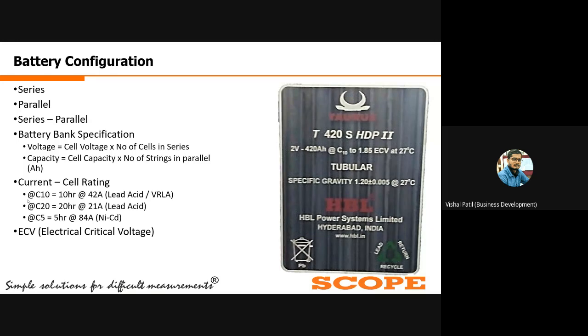So that's why it is very important to maintain the cell voltage above ECV. Generally this ECV is 85 to 90% of the nominal voltage of the cell.